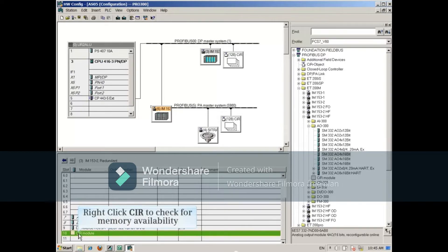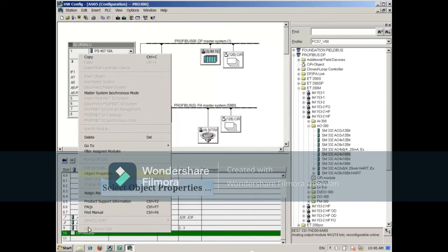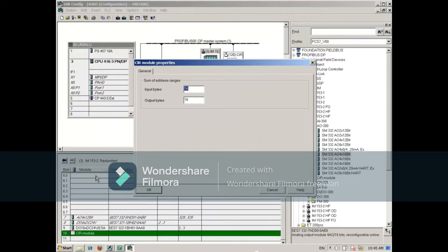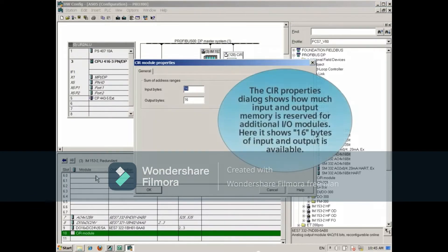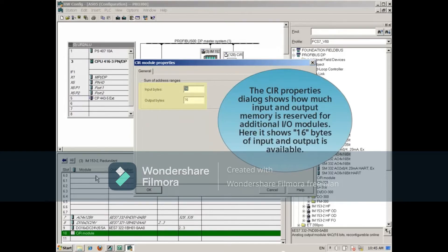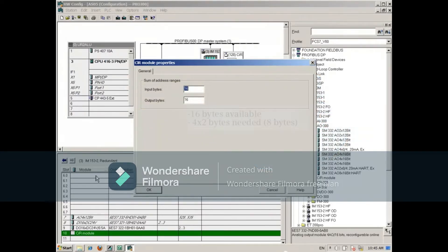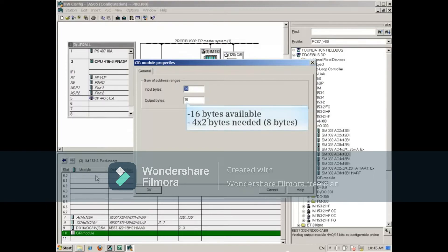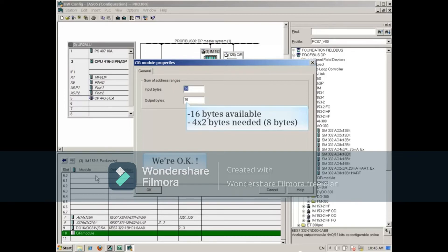To check if it has enough memory to allow the addition of the AO module, right-click it and select Object Properties. The CIR properties dialog shows how much input and output memory is reserved for additional IO modules. Here it shows 16 bytes of input and output is available. The output module needs 4 times 2 bytes, or 8 bytes total, so we're okay.